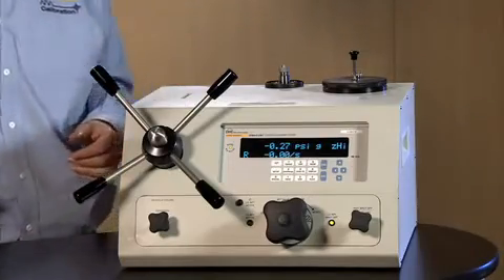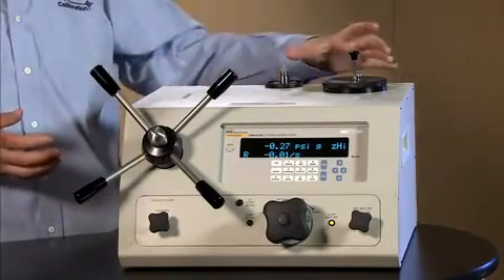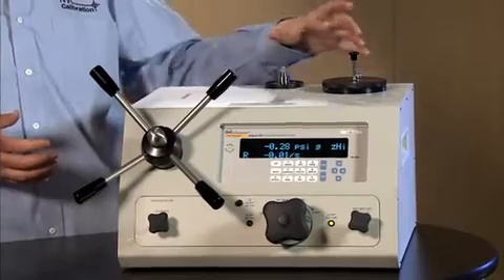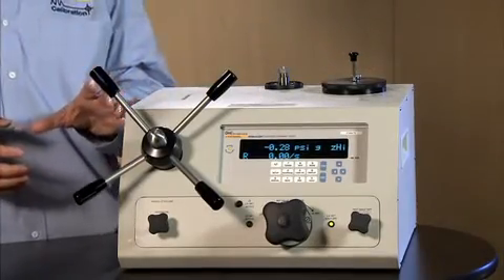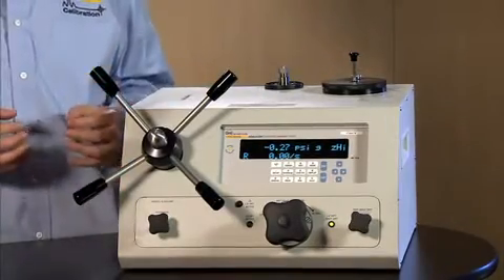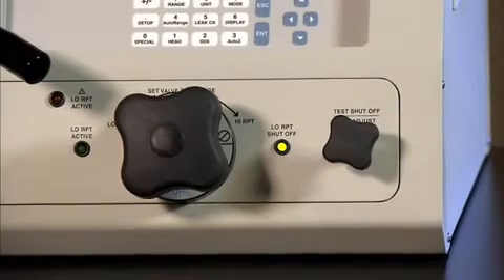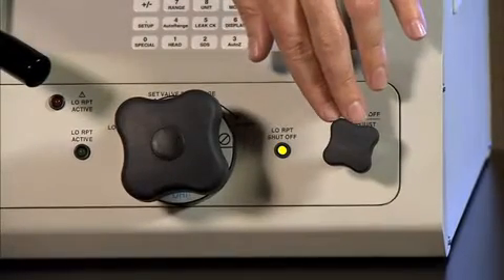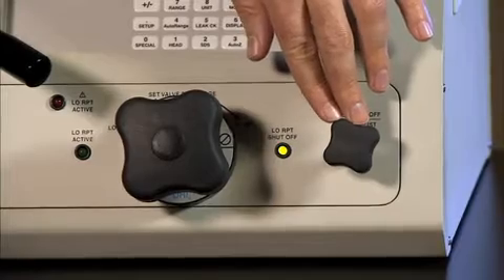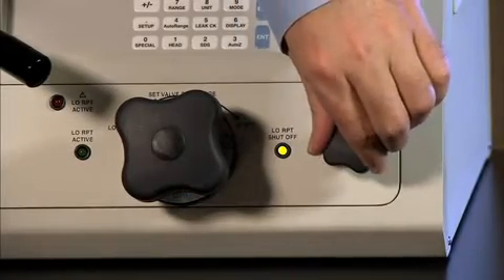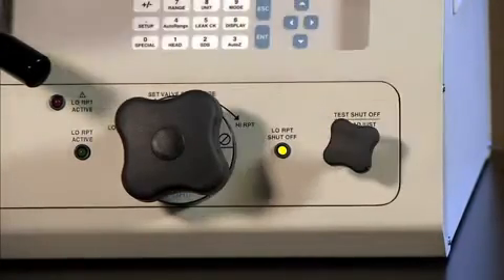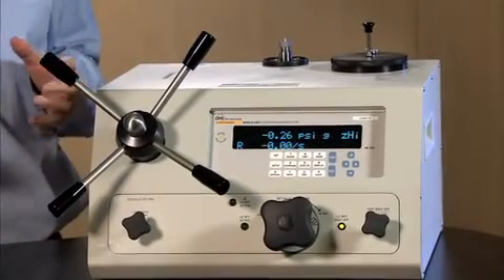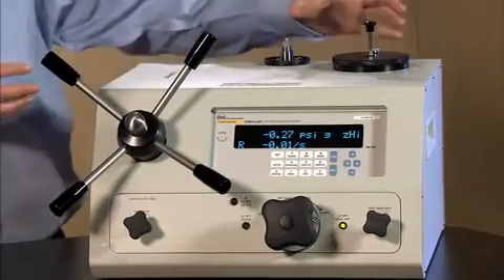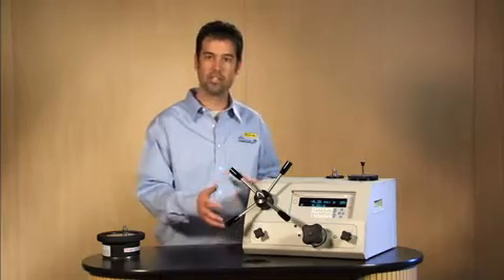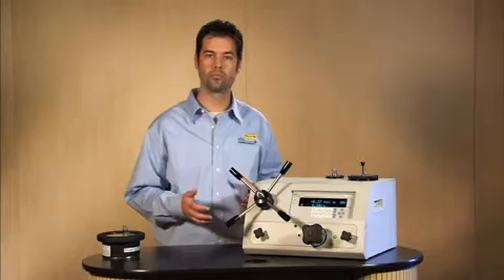Now we want to extract the fluid from the reservoir and fill the variable volume so that we have the maximum stroke for when we go to calibrate our gauge. We also want to orient the test shutoff valve so that it is closed. Closed is fully clockwise. It does not have to be fully tightened, it just has to be snug. Now the valves are in the correct orientation to pull fluid from the reservoir into the variable volume.